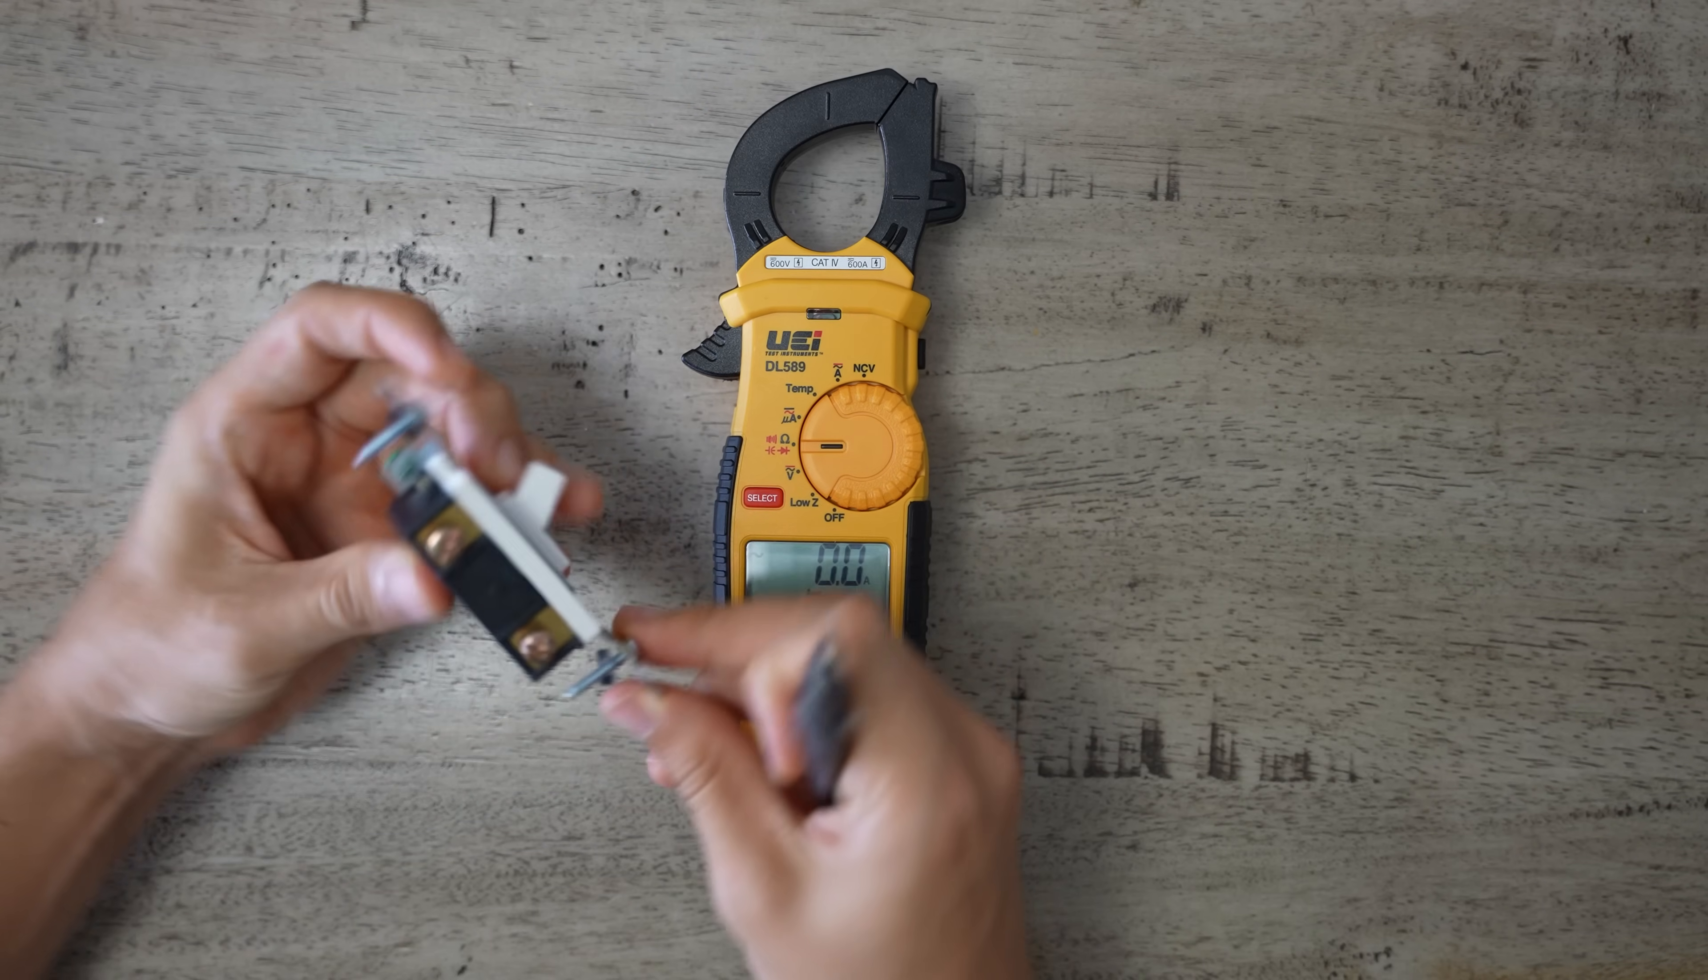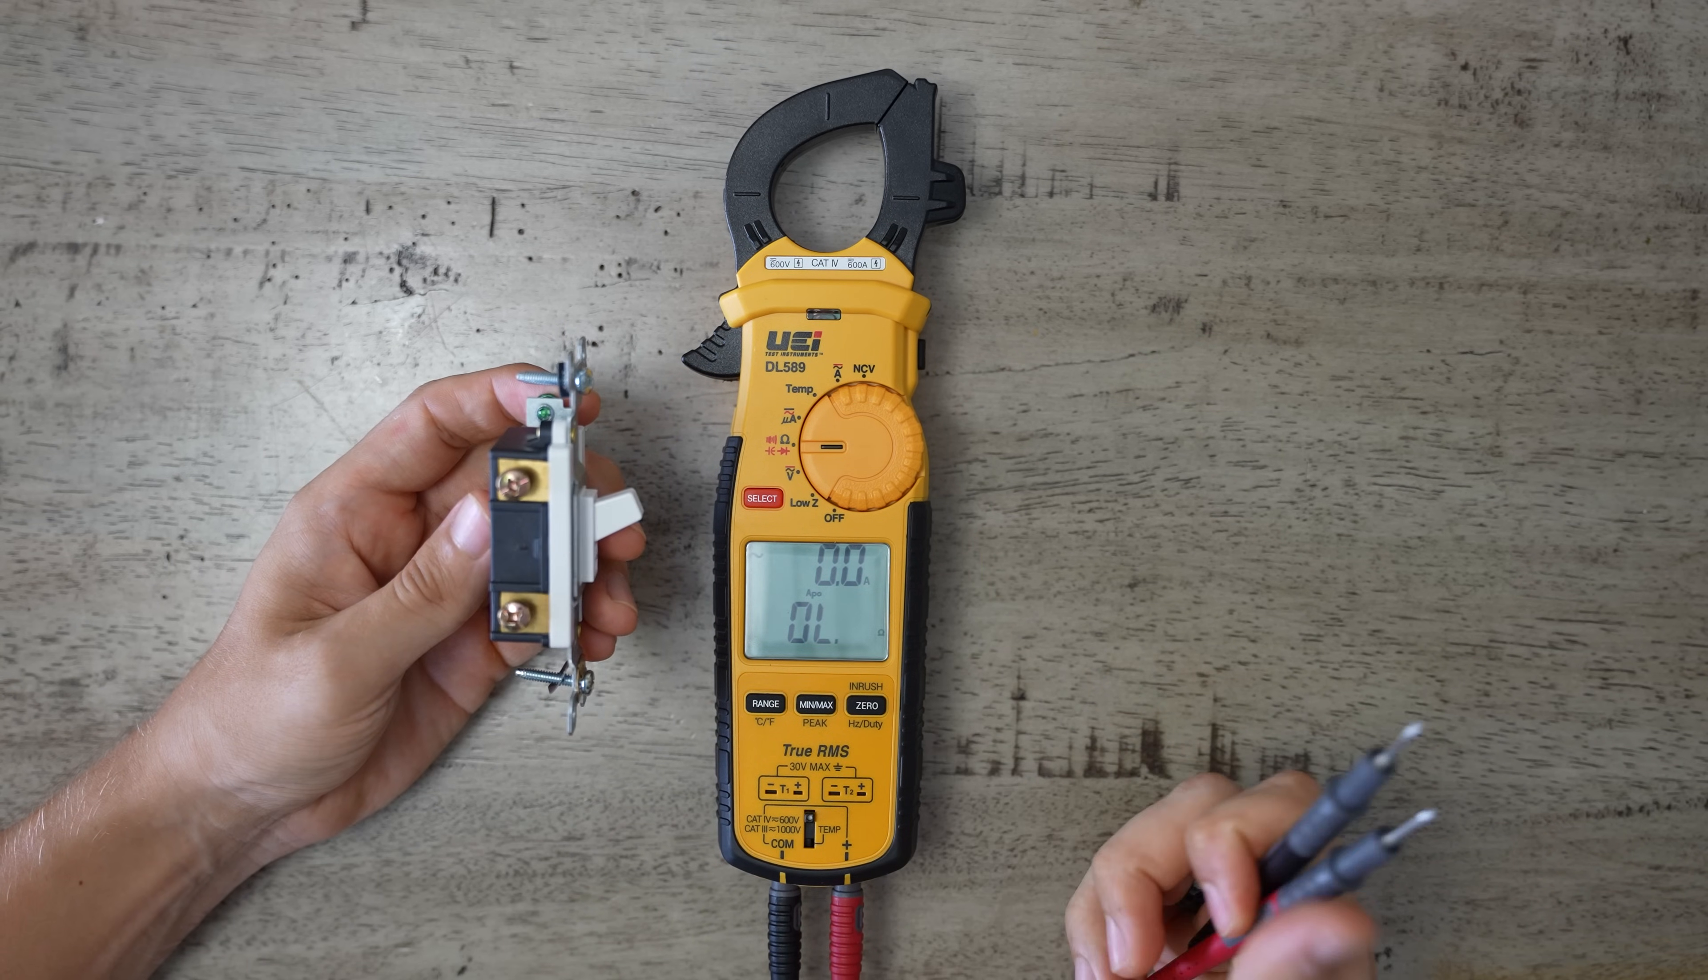For example, if we take this light switch right here, usually there will be wires going to it. If you wanted to check the resistance of this light switch, you have to take the wires off before you check the resistance, and the power has to be off. If the power is off, but the wires are still on, you're going to get a false reading, because you're also reading the wires along with the switch.